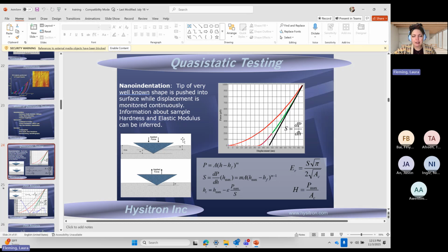So we have this probe that is being pushed into the sample, and from the force and displacement information we get out of the transducer, we're able to then calculate hardness and modulus. So we have this loading and this unloading. We then do a power law fit to the unload. And when you take the first derivative and fit at the maximum, you get the stiffness of the material. From that stiffness, we get a lot of other information.